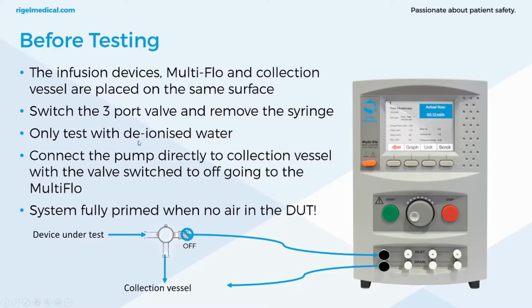And now we're going to do testing with deionized water. You can use distilled water as well. It does say only test, but you can use distilled water. So here we've got the device under test going direct to the collection vessel. We've shut off the flow to the infusion pump, so there's nothing flowing to the collection vessel from the Multi-Flo. And then we connect the pump directly to the collection vessel with the valve switched off.